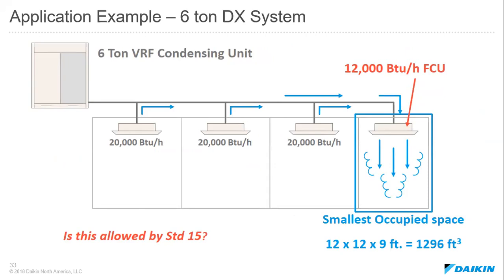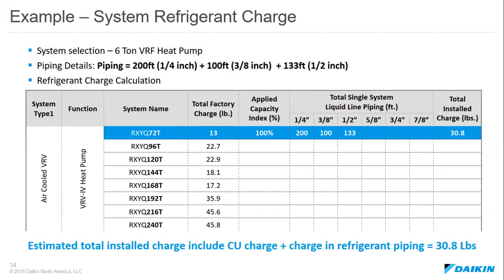If we have a 6-ton DX system, so we have a 6-ton VRF outdoor unit, and we've actually got 4 different closed off occupied spaces here. The first 3 spaces have 20,000 BTU indoor units, and then at the very end of this system, we have a 12,000 BTU fan coil unit that is located in our smallest occupied space, which is actually 1,296 cubic feet. So the question is, is this allowed by ASHRAE Standard 15? To figure that out, how much charge is going to be in that system is going to be our first step here.